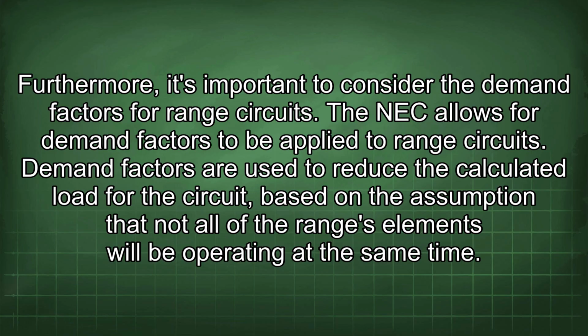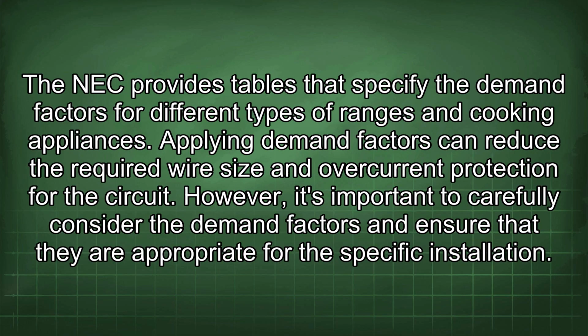Furthermore, it's important to consider the demand factors for range circuits. The NEC allows for demand factors to be applied to range circuits. Demand factors are used to reduce the calculated load for the circuit based on the assumption that not all of the range's elements will be operating at the same time. The NEC provides tables that specify the demand factors for different types of ranges and cooking appliances. Applying demand factors can reduce the required wire size and overcurrent protection for the circuit. However, it's important to carefully consider the demand factors and ensure that they are appropriate for the specific installation.